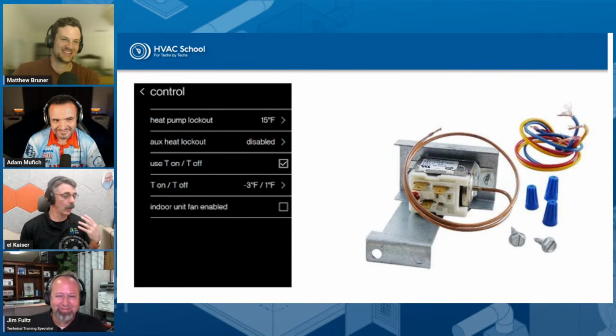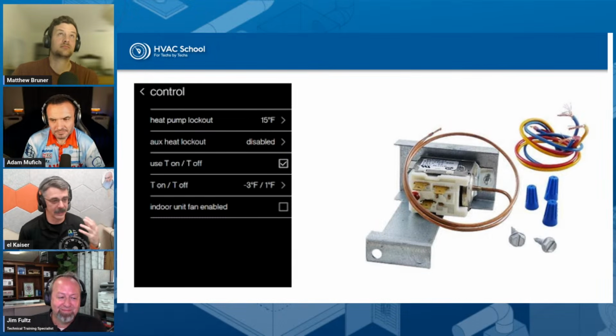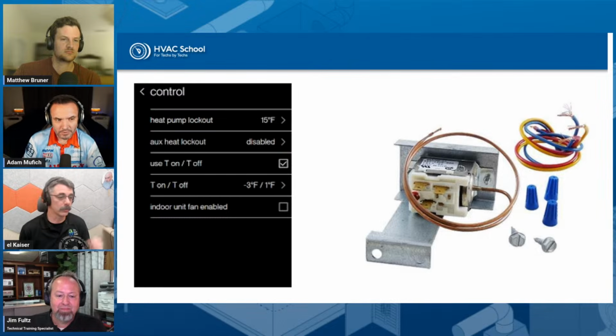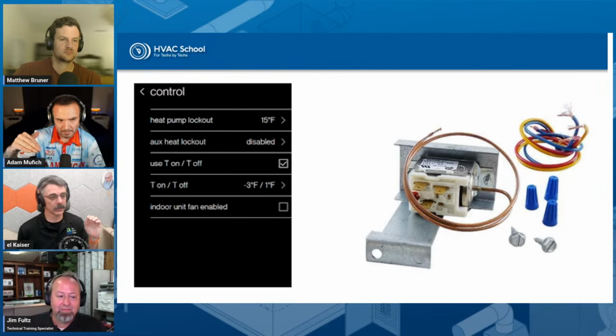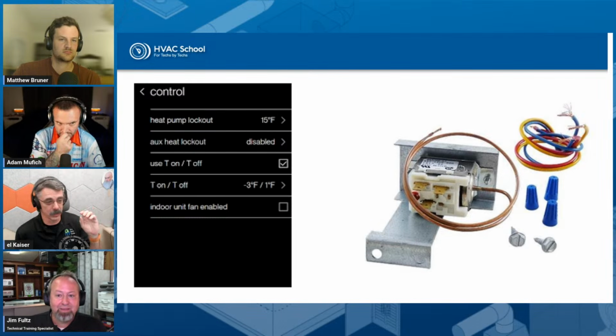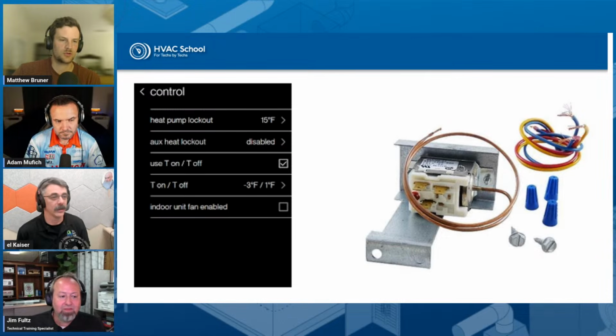Well, we always wired in an outdoor thermostat to activate that auxiliary heat. And everybody else just banged everything on, they might be banging on 10, 15 kW of heat. Well, we would bring on heat by temperature. Oh no, they would just bang it on with the second stage heat call. Oh, okay. So if there was a droop, then it would just... If there was a droop, man, it was bang.